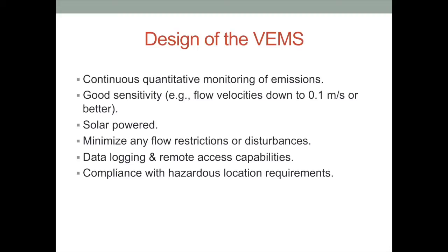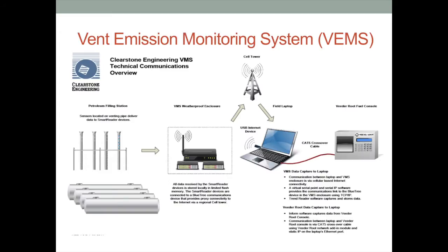For data logging, both panels are remotely accessible and data is sent back to our office using cellular communications. We have diagnostic systems that monitor the incoming data and check for faulty instruments and problems with the system. We're polling the devices at a rate of once every six seconds, giving us a fairly large data set over the monitoring period. Of course, we also had to comply with the hazardous location requirements for putting equipment around storage tanks, and that was all done to meet the requirements of the operators at these sites.